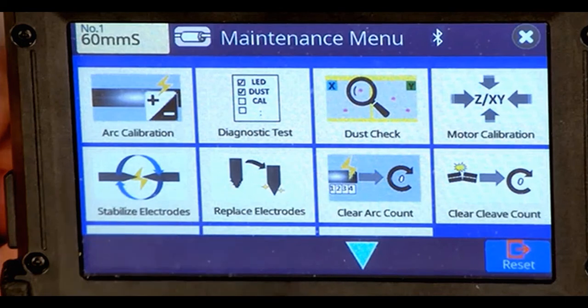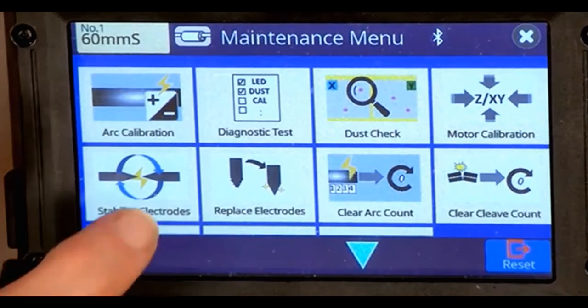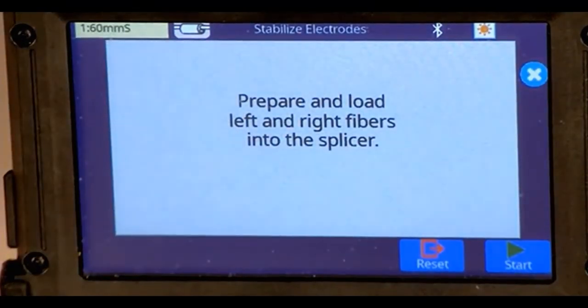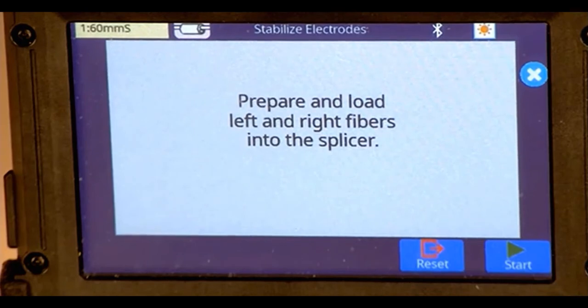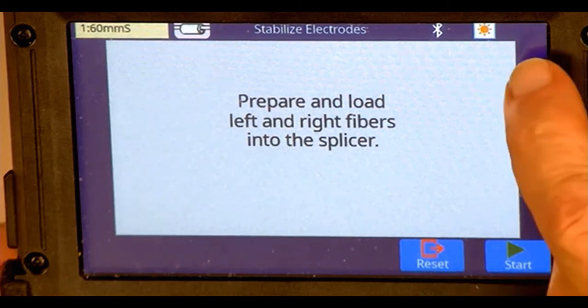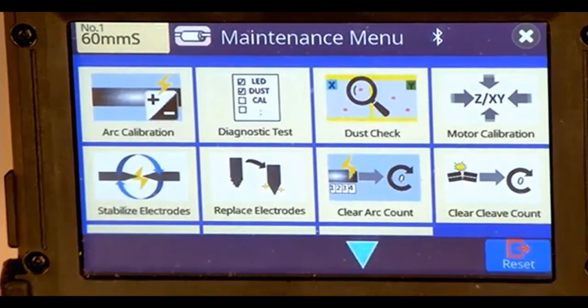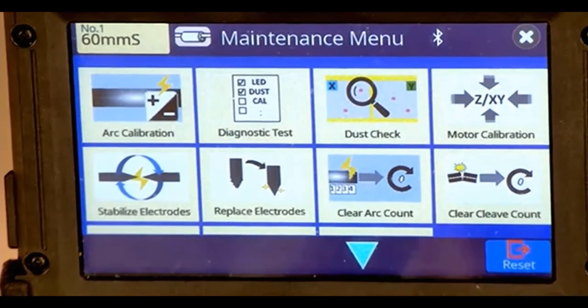This is the stabilized electrode thing that I told you about. So if you have unstable electrodes, you can go in here and press this. It's going to tell you to load fibers. You strip, clean, and cleave fibers like you would for splicing. And what it's going to do is splice and arc multiple times and try and build up some silica deposits on the electrodes, which hopefully will then make that electrode condition good. And you would want to, after this, do an arc calibration and make sure it's okay. So sometimes if you've accidentally touched the tips of the electrodes, you can get it to function properly by doing a stabilization. It won't always work. You know, if you've really damaged the tip of the electrode, then you're just going to have to put new electrodes in them.